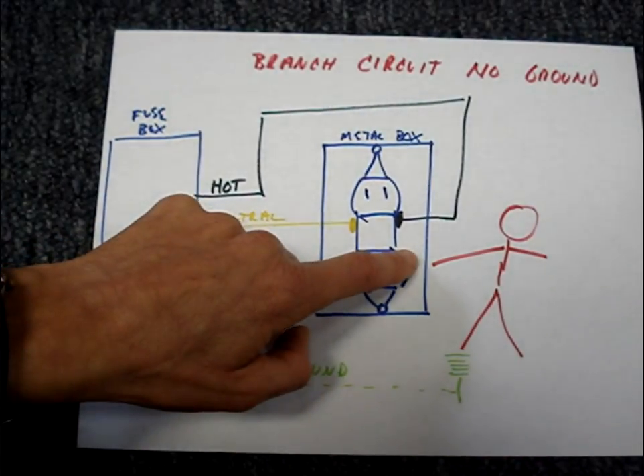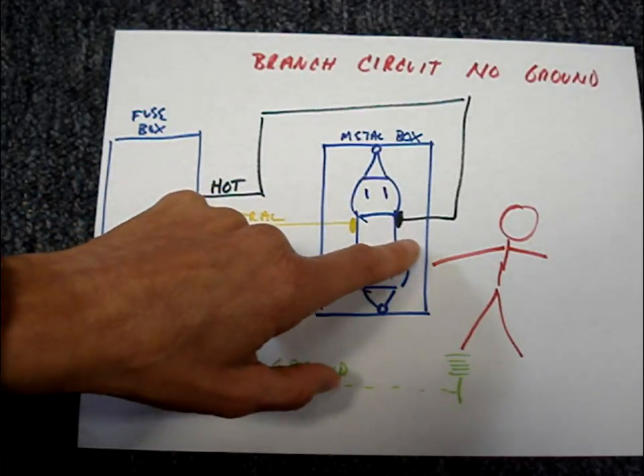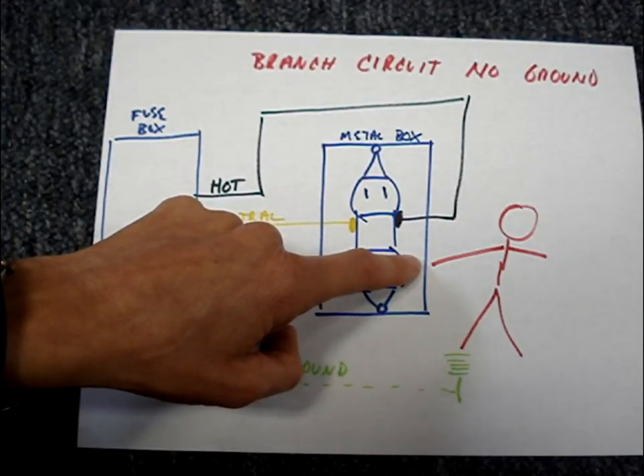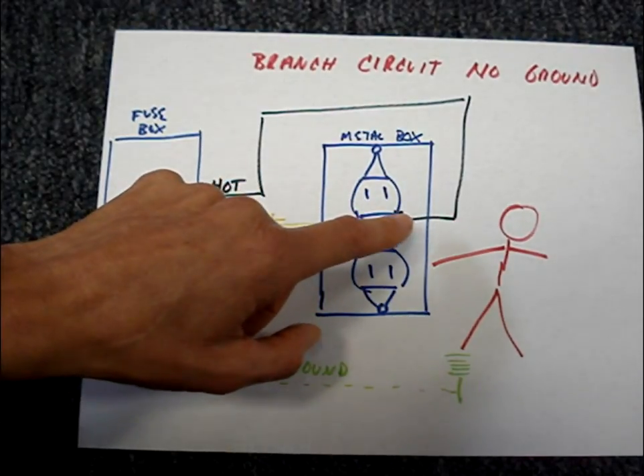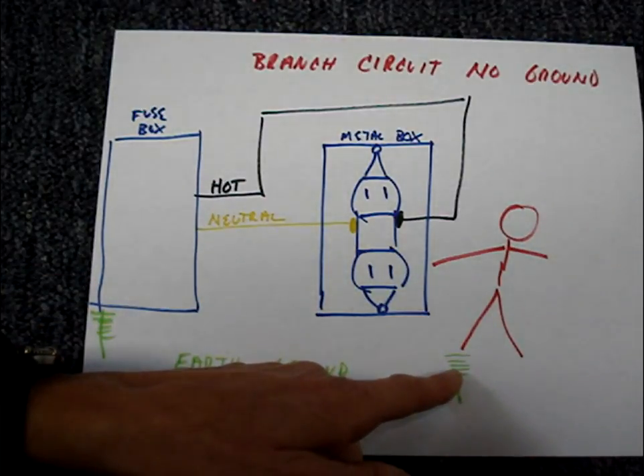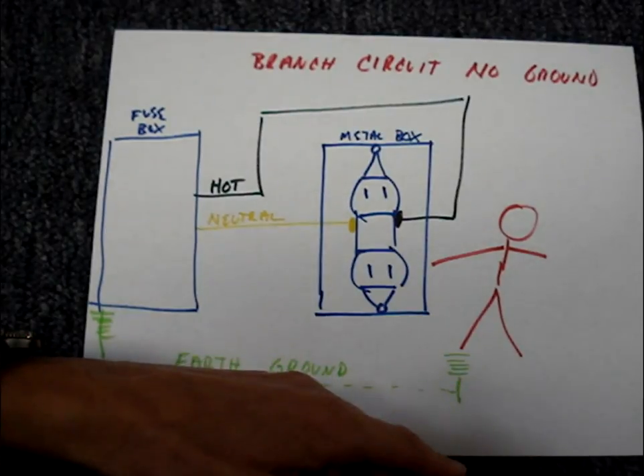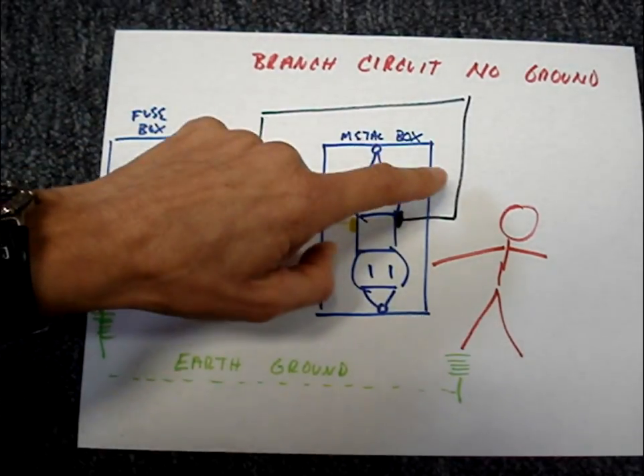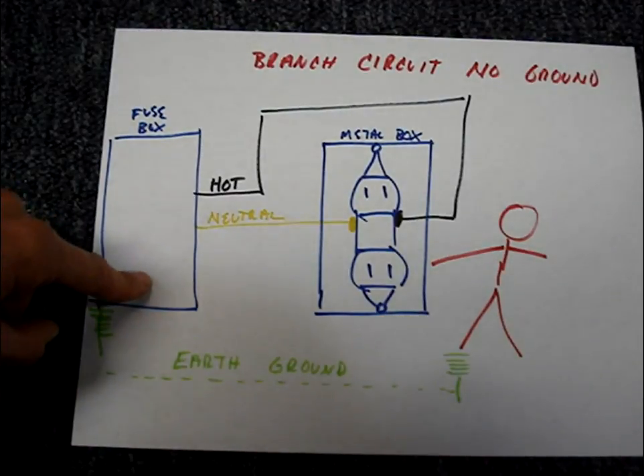It would be energized and if a person came along and touched this box, you would get a shock. If you were standing in some water and didn't have any shoes on, that may be the right conditions to complete the path for current to go back to the source through ground.